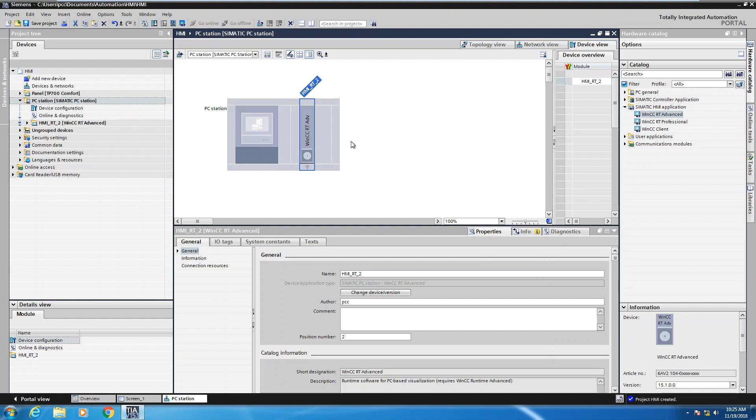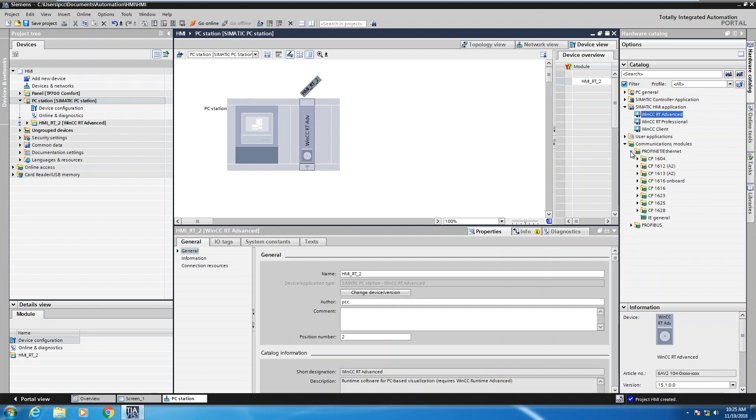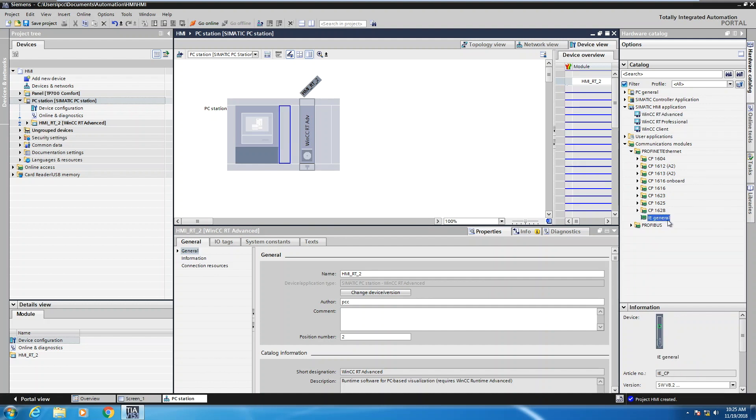The next is I have to add in the type of interface or what type of communications I'm going to be using. So that would be in the communication module section over here. And I'm going to select PROFINET slash Ethernet. This will give me a listing of higher end CP cards that can be added into the PC. Or I could select the IE General, which would be just a standard Ethernet interface on your PC. So I'll drag the IE Ethernet into the slot over here.